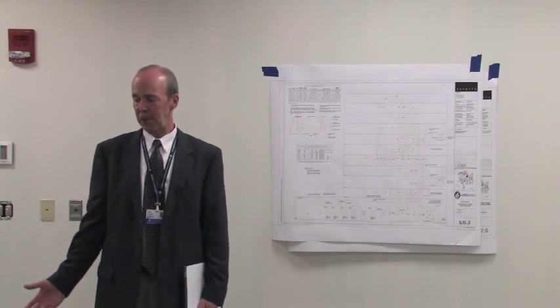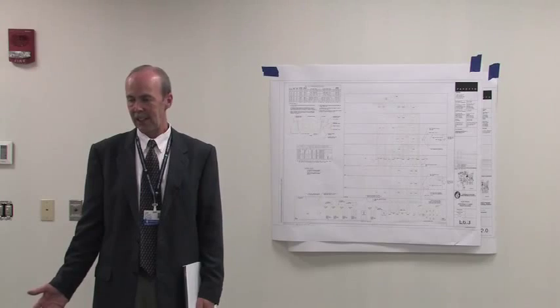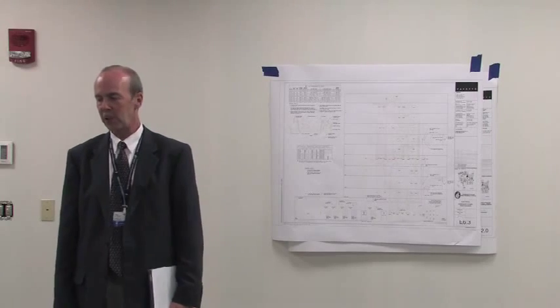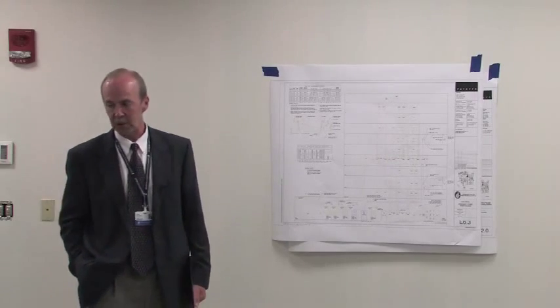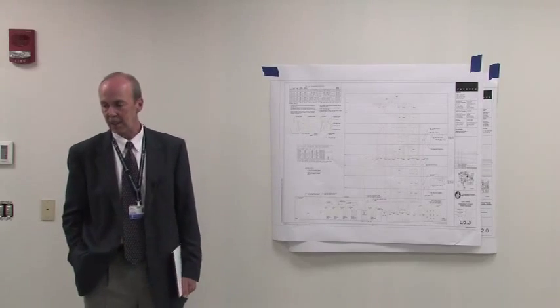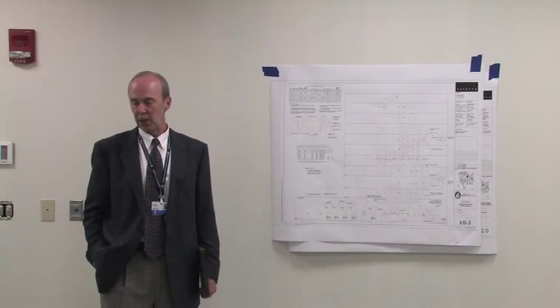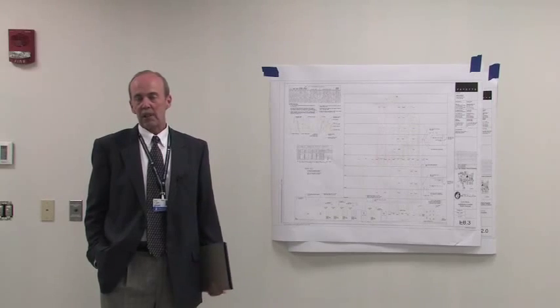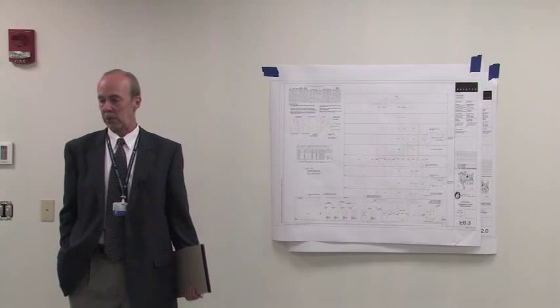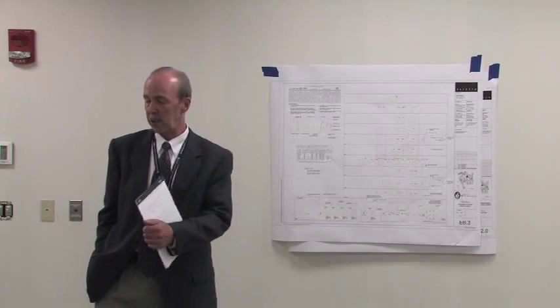This building is not going to be a big net add. Oh no, we're gonna find out though. I'd be very surprised if the emergency load in this building is going to be that high, I really would. Typically you're going to go 2.5 to 3.5 watts a square foot on your gen sets. That's what you've got in here now.